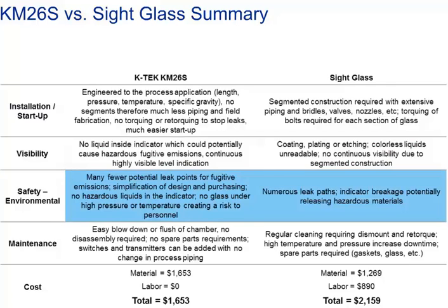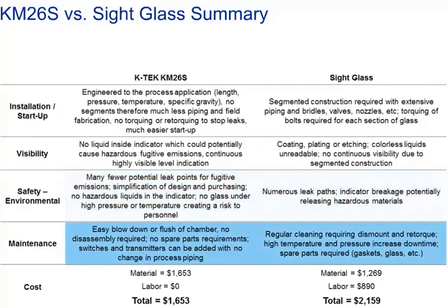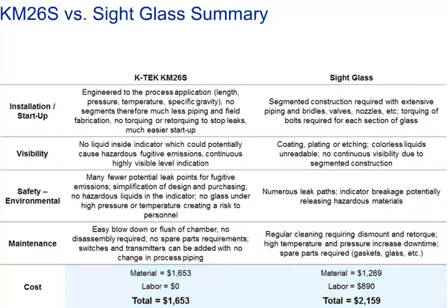In addition to the potential problems with sight glasses, extensive maintenance is required to keep them clean and leak-free. The bottom line: the KM26 offers continuous level reading, simplified design and installation, easy flushing should cleaning be necessary, fewer potential leak paths for fugitive emissions, no hazardous liquids in the indicator glass, and no glass under high temperature or high pressure causing risk to personnel.